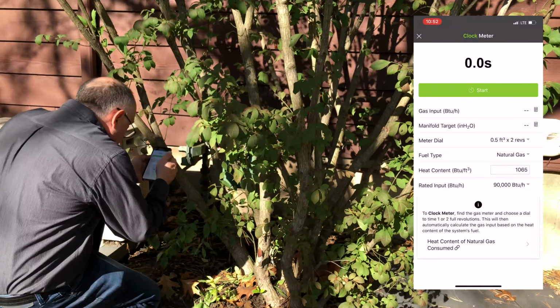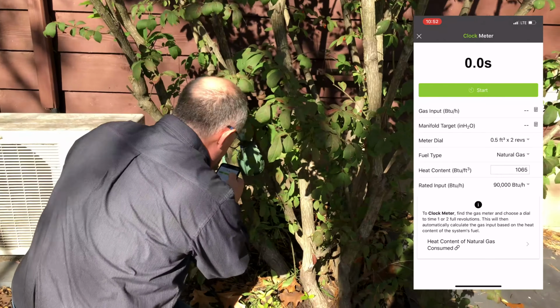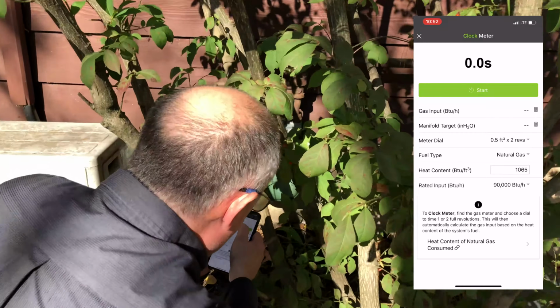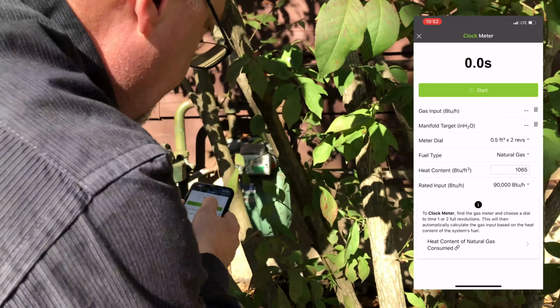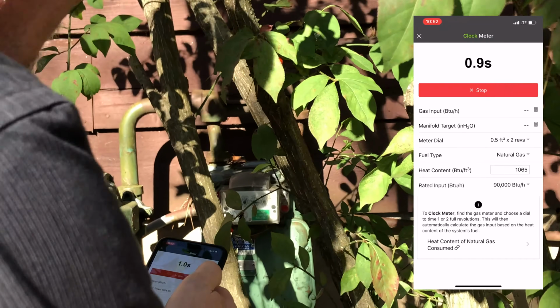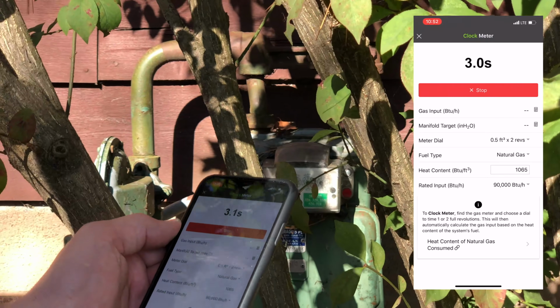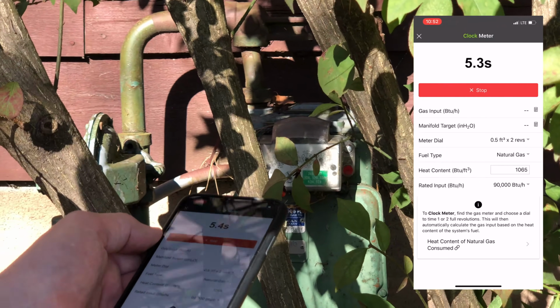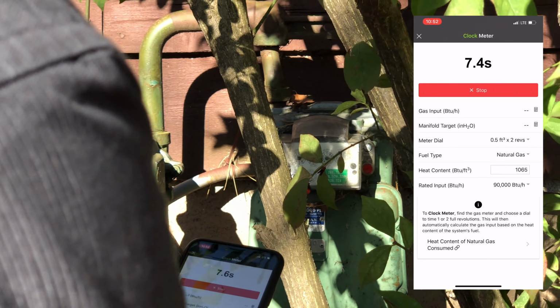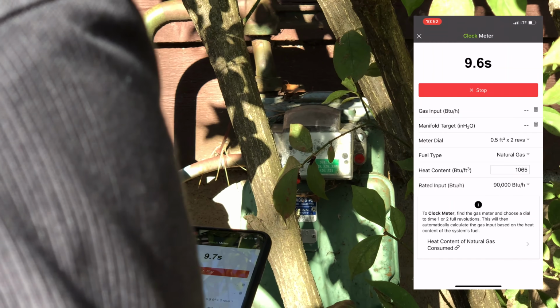So here I want to wait till the 1/2 inch dial gets to the top here where I can see it go. When it crosses the top, I'm going to hit start. We've got to let that go around for two revolutions. It's a 1/2 cubic foot dial, so it's got to go around 2 times before we stop the meter.